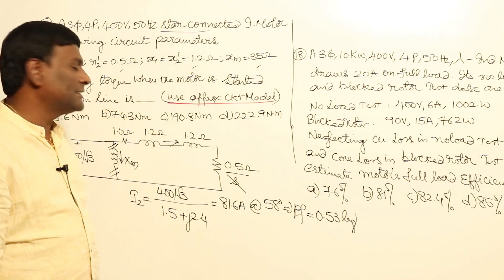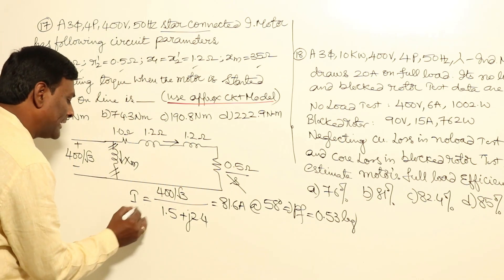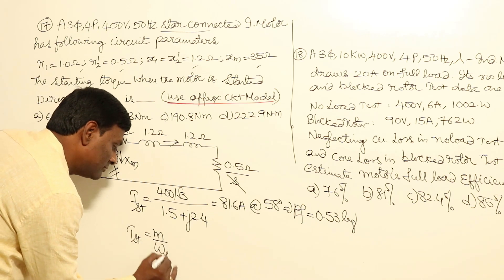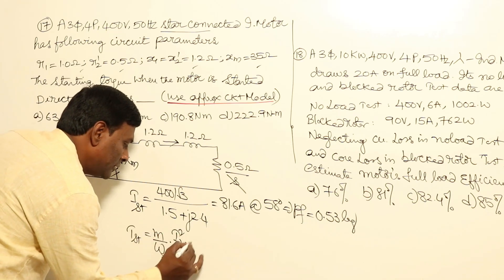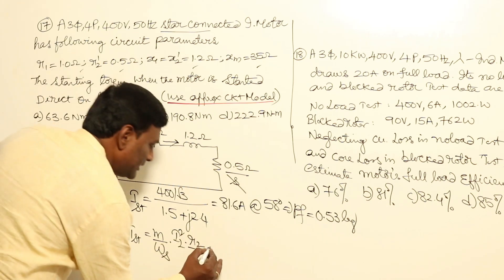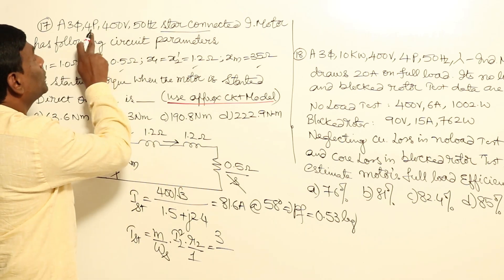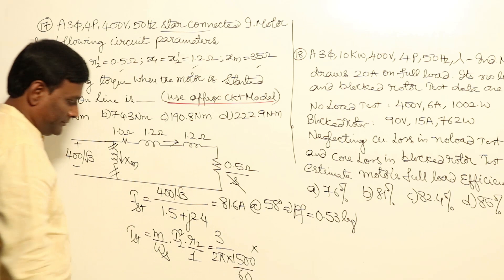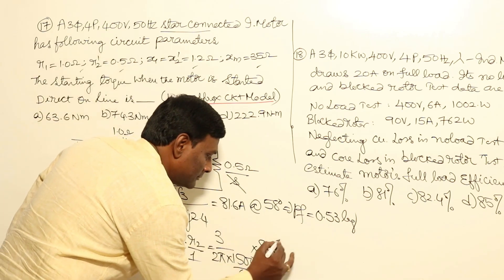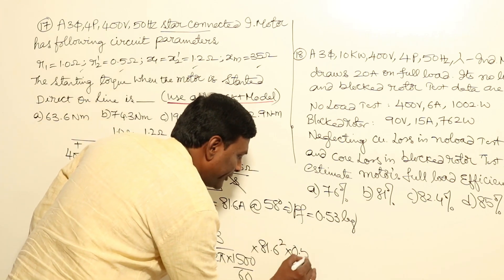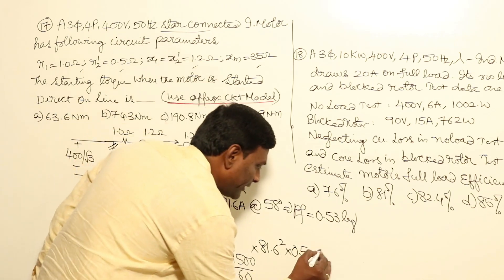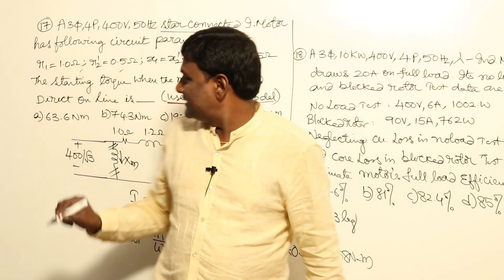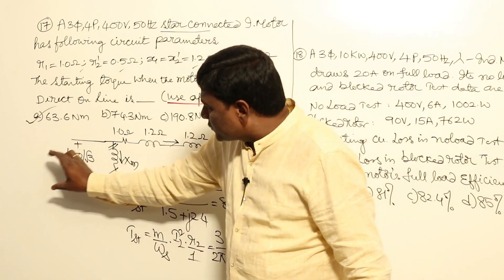The starting current I2 equals 81.6 A. The starting torque is: T_start = (3 / ωs) × I2² × (R2/S). With S = 1 and 4-pole, 50 Hz motor, Ns = 1500 rpm, so ωs = 2π × 1500/60. T_start = (3 / ωs) × 81.6² × 0.5, giving an answer of 63.58 Nm.